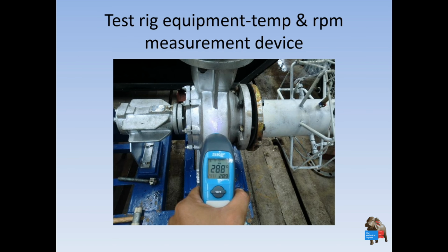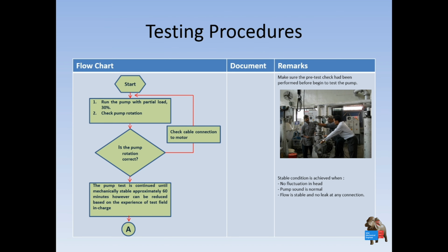Another piece of equipment you may need is a temperature sensor. These are infrared temperature sensors, and you also need RPM meters, infrared with a deflector, etc., to measure the pump's shaft rotation during the testing. Next, we have a testing procedure that we have to follow.